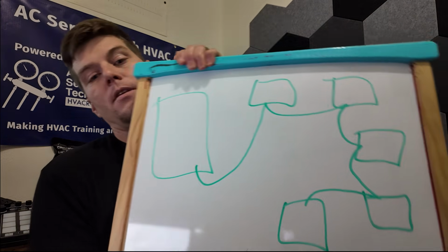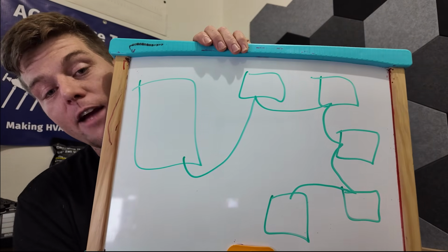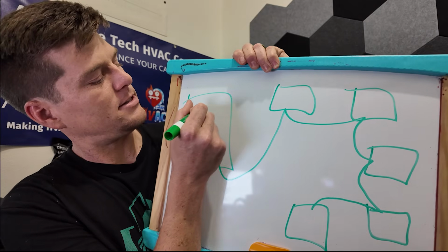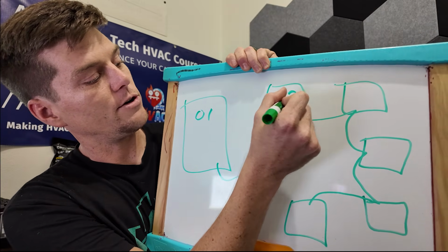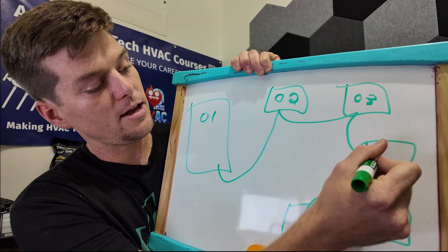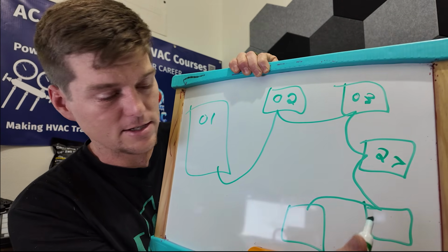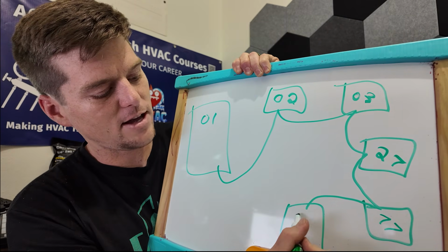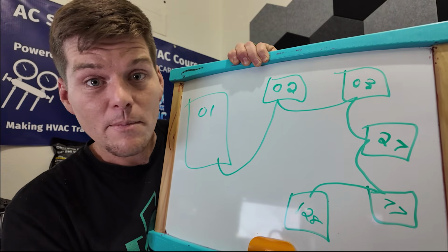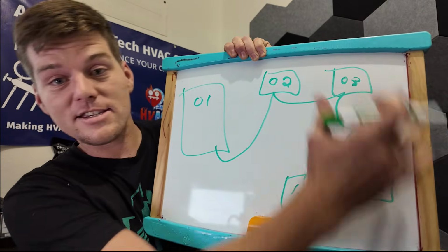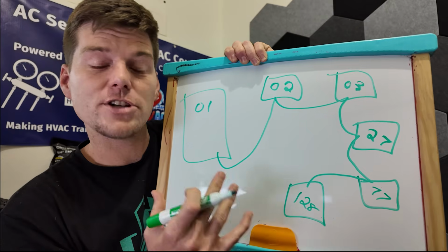That's right, when you have a system like VRV, everything gets auto-addressed. What does that mean, auto-address? Well, with an auto-address system, you're going to find that when you turn the power on for the first time, in the communication circuit that looks like this, everybody gets an address. The outdoor unit gets an address. Hey, you're 01. You're 02, 03, 27, because machines don't make sense when it auto-addresses. You're 77, and you're 128. Why? Because of reasons unknown. This is the address system that it creates on the first time it powers up.